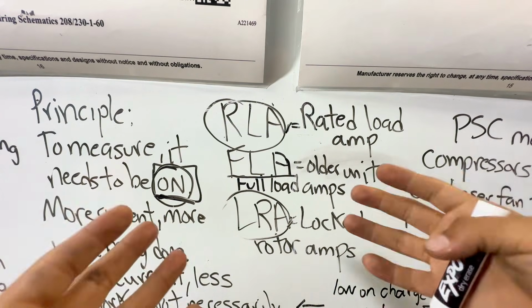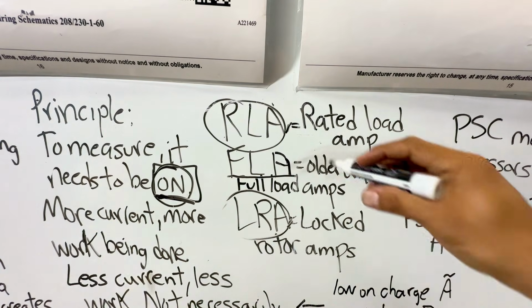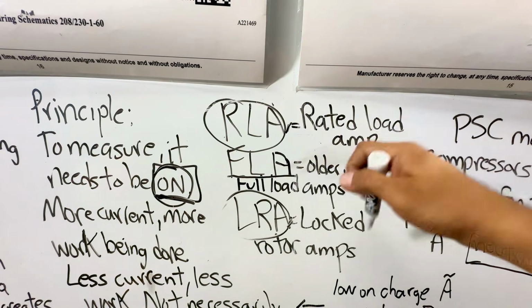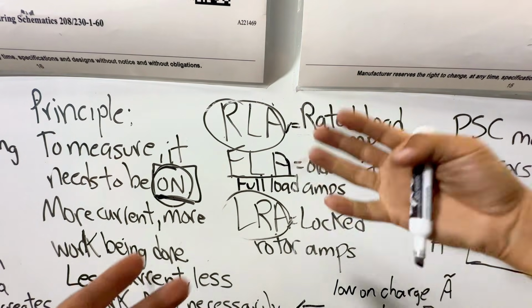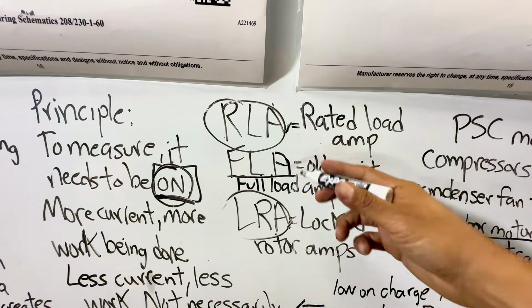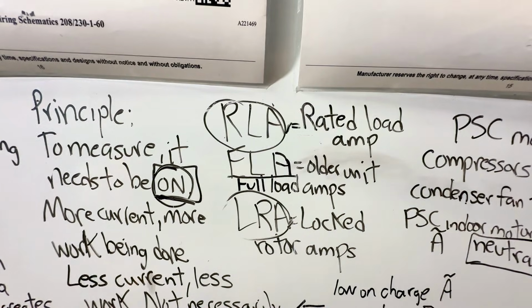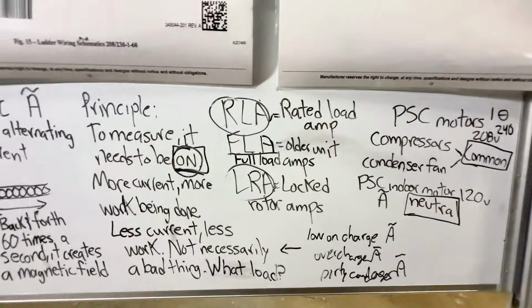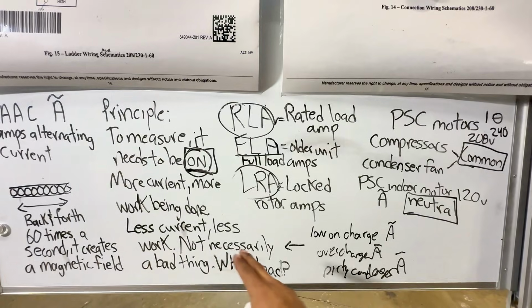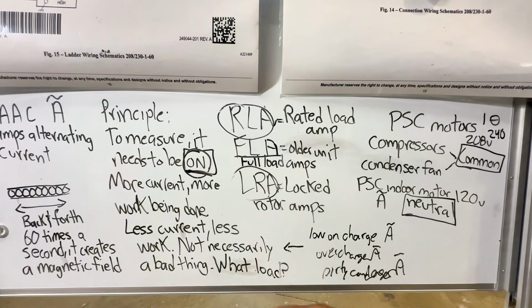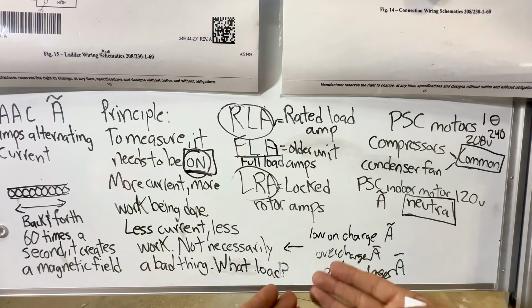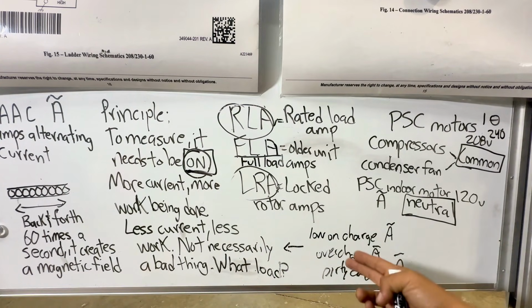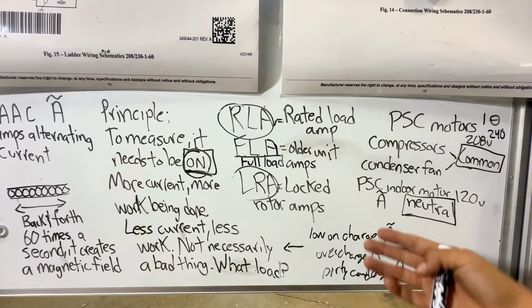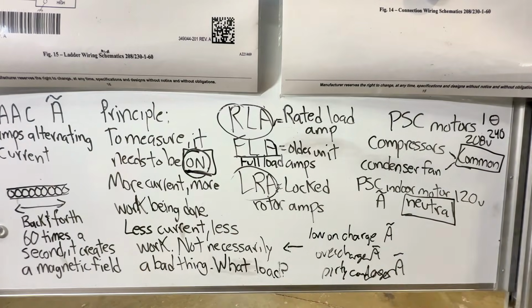But today I'm just gonna show you how to check amp draw. Just know that in compressors, you'll see RLA. In condenser fan motors and other motors, you'll see FLA for the most part, okay? But like I said, when it's less current than usual in the case of the compressor, which I'm going to show you in a bit, that tells you, hey, it could be low on charge. It could be overcharged because it's pulling too much current. Maybe it has a dirty condenser.